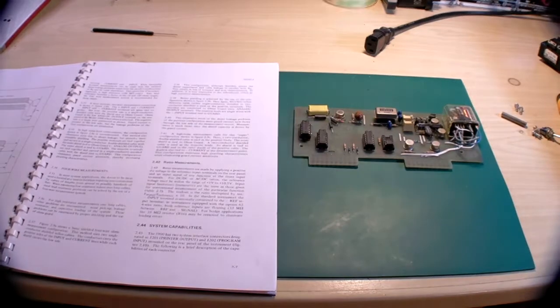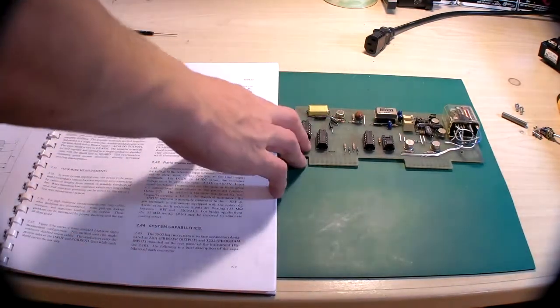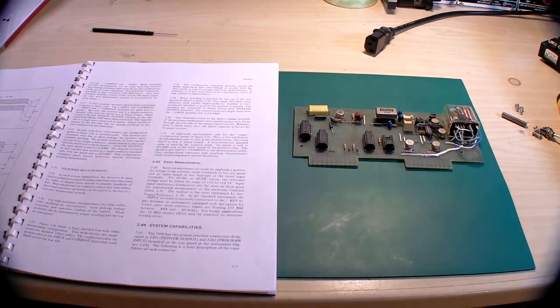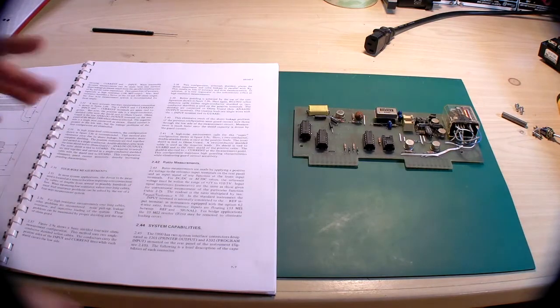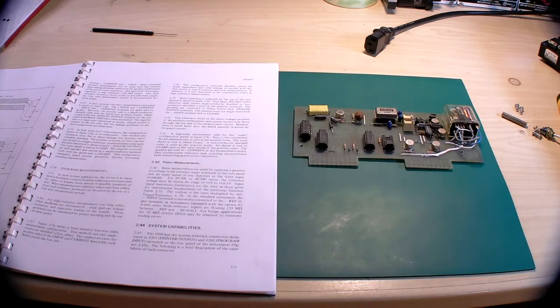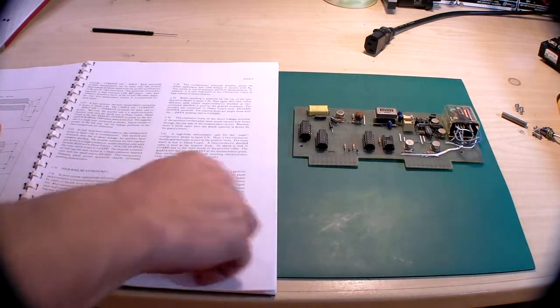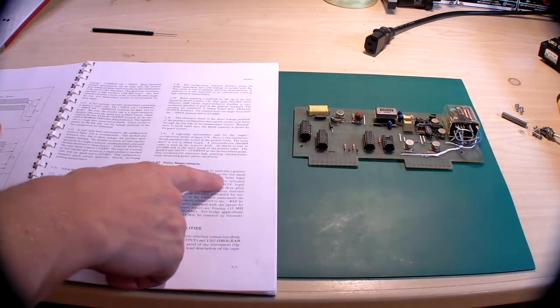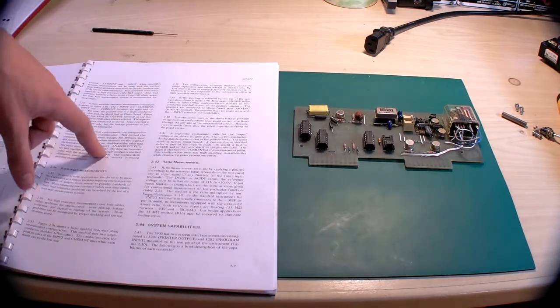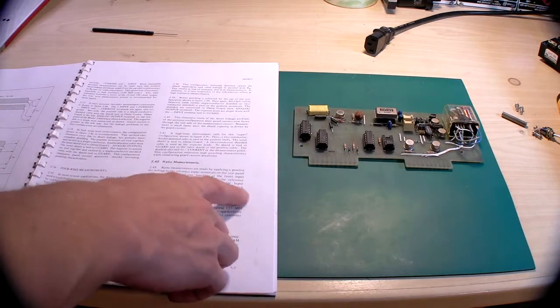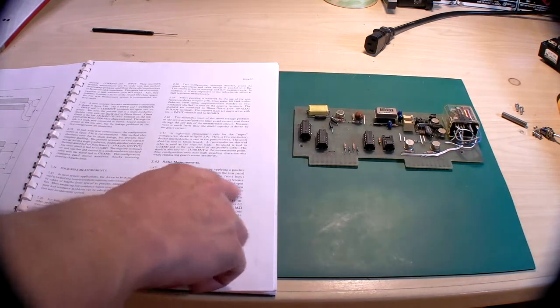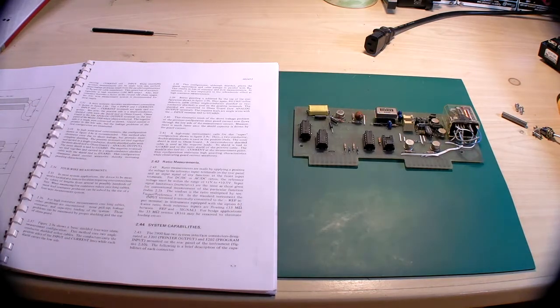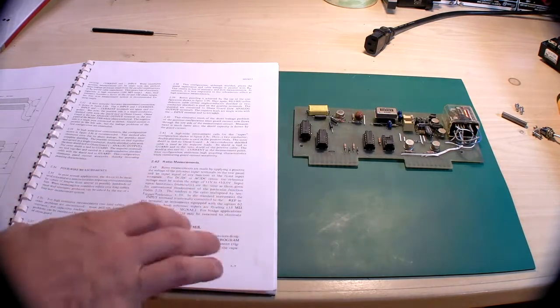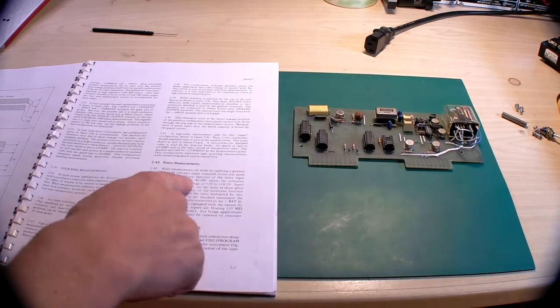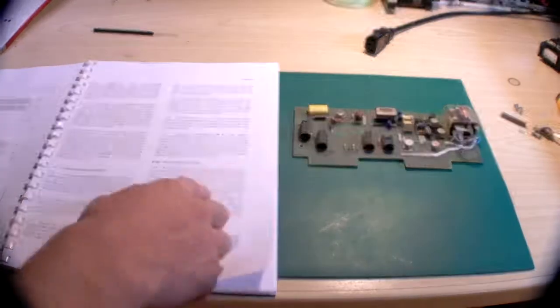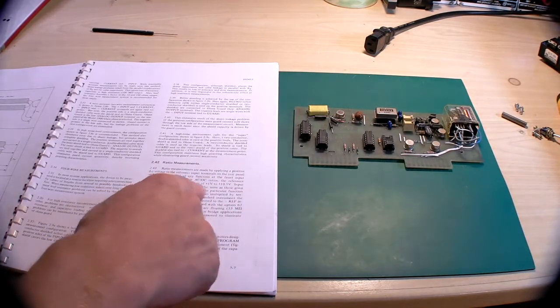After a little bit of research, I think I found out what this mod was for. I believe the unit was modified for a different type of ratio measurement, and it's right there on the manual. It says ratio measurements are made by applying a positive DC voltage to the reference input terminals on the rear panel. My model here is equipped with option 62, which allows a 4-wire ratio measurement. For DC or AC/DC ratios, the reference voltage must be within a certain range.